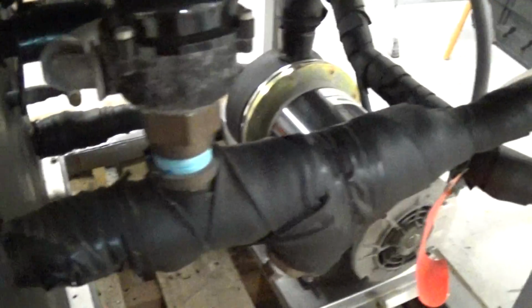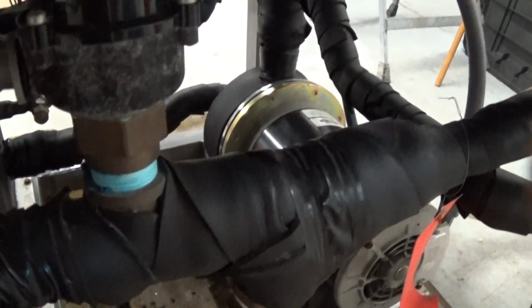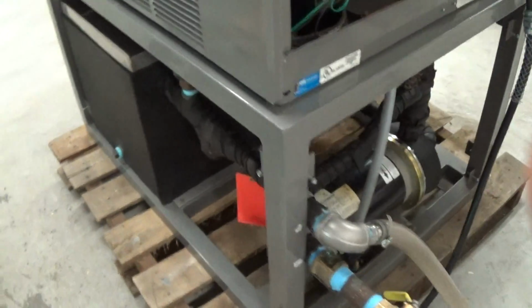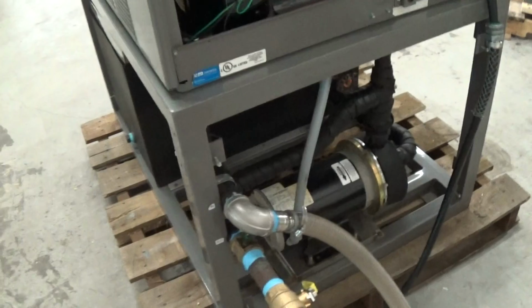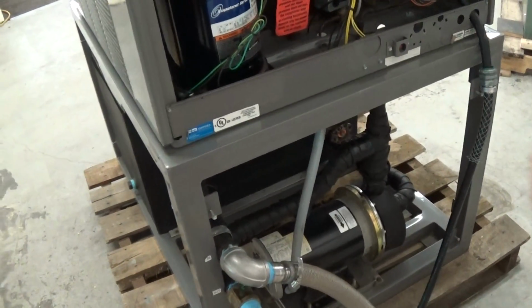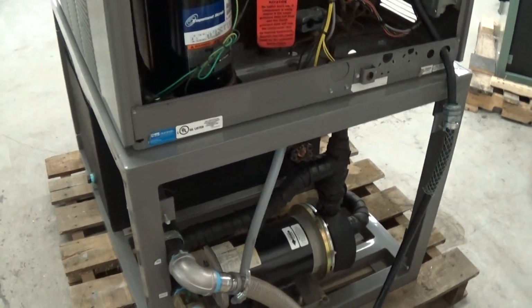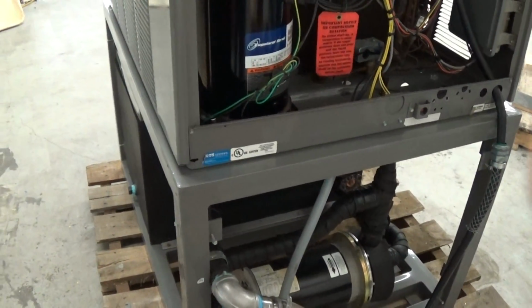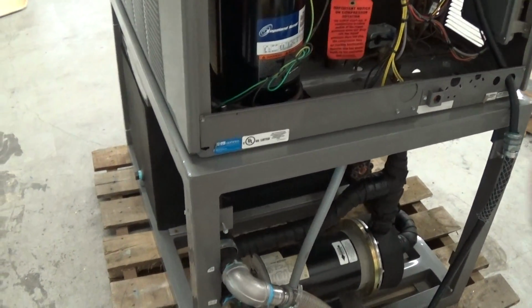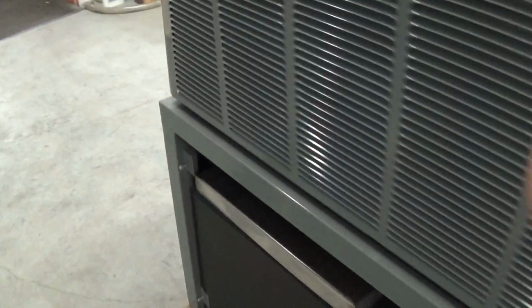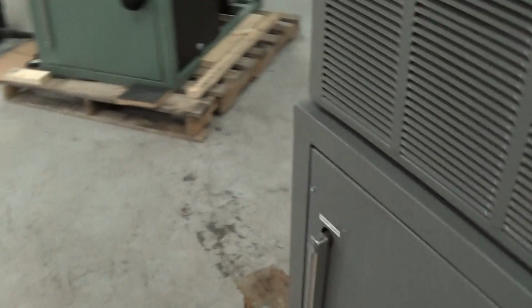In this design unit, we have our flow switch here, and it's kind of tough to see, but in here in the tank, that's where we have the braze plate heat exchanger submerged within the tank, which is kind of nice in case it ever gets a little bit too cold or ices up, which really shouldn't happen if you have the appropriate amount of glycol, but it does allow it to thaw out very quickly. And as I mentioned, we do have all the side covers of the unit. It'll ship with them on there.